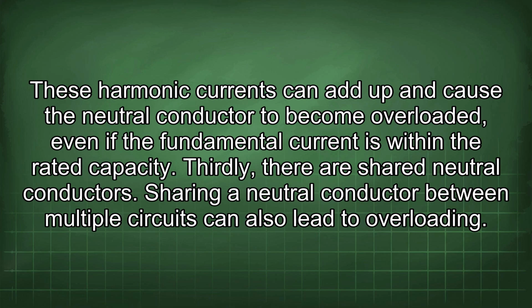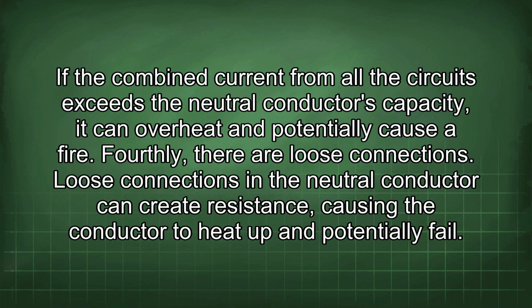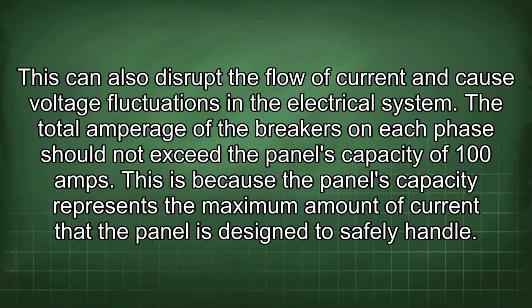Sharing a neutral conductor between multiple circuits can also lead to overloading. If the combined current from all the circuits exceeds the neutral conductor's capacity, it can overheat and potentially cause a fire. Fourthly, there are loose connections. Loose connections in the neutral conductor can create resistance, causing the conductor to heat up and potentially fail. This can also disrupt the flow of current and cause voltage fluctuations in the electrical system.